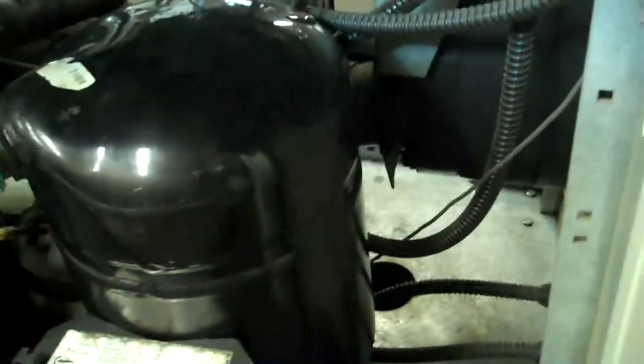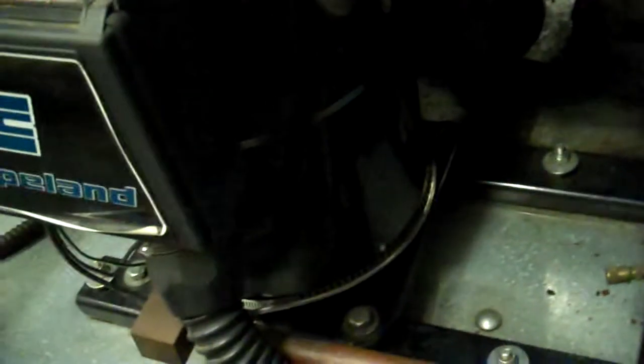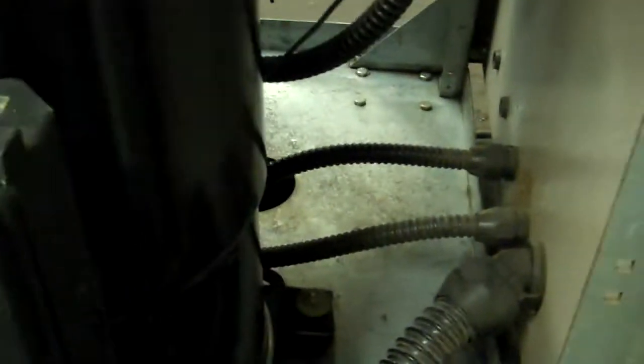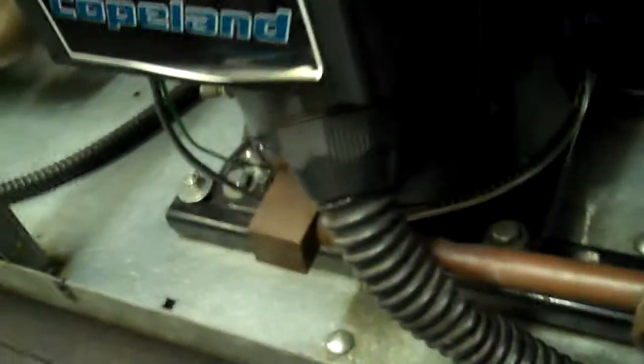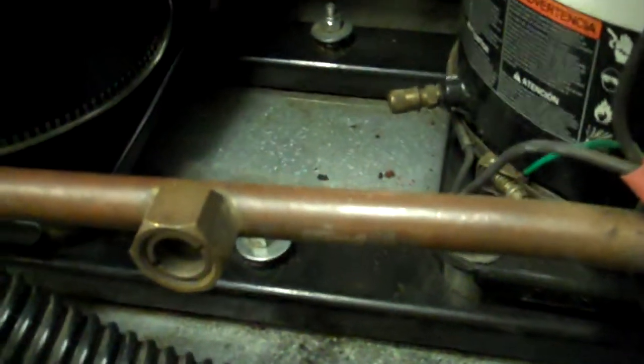We have our 2 15 horsepower Copeland compressors. Both of them have heater bands. It's good before you ever start this chiller up to make sure you have power to the unit for several hours. Let those heater bands provide some heat to the bottom of the compressor area. The chillers are connected in tandem from an oil point of view. That's an oil sight glass there.